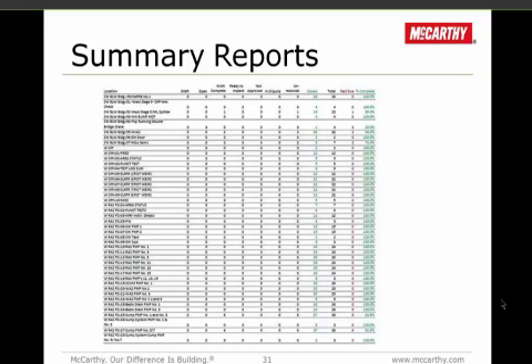Is the pump motor wired? Have they been measured? You just see the progression of items moving to 100% complete, which allows you to start doing the mechanical checkout with the actual manufacturer, bumping the motor, starting to pump fluid to verify the operation of the pump.